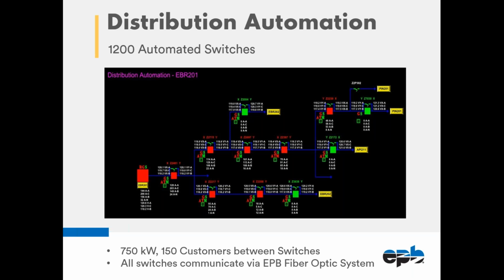The way the distribution automation technology works is that if we have a fault, say between two switches, the switch upstream would recognize the fault and open to interrupt it. It would communicate with the switch downstream to open so the fault is isolated, and then communicate with another open switch that could close to restore power on the back half of the circuit.